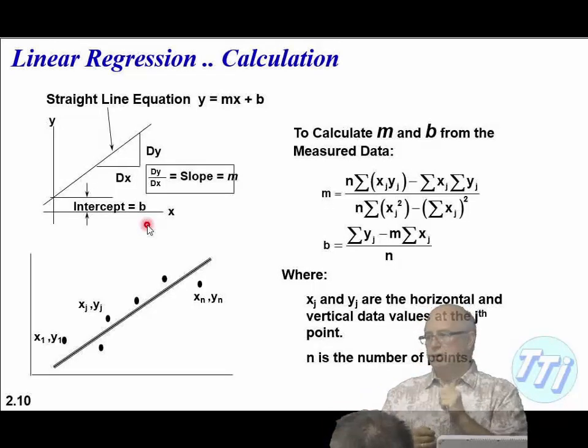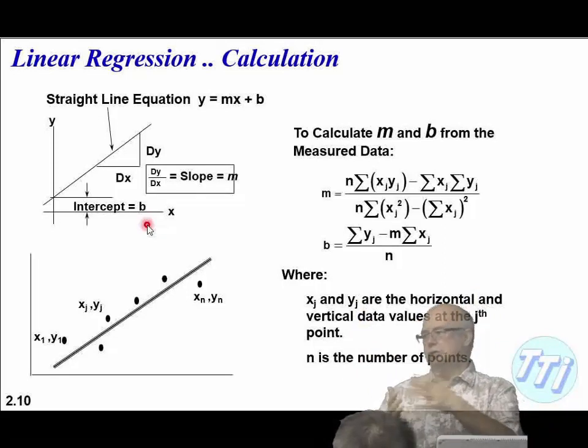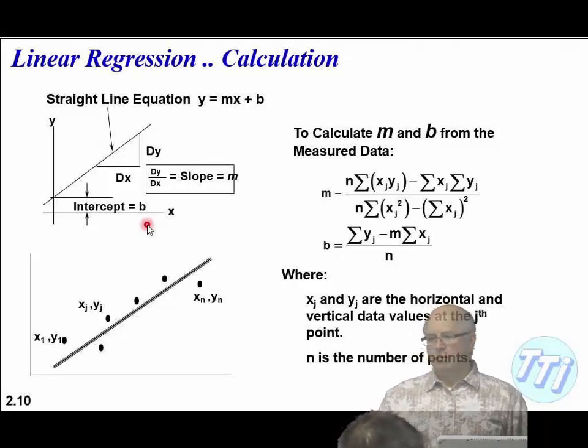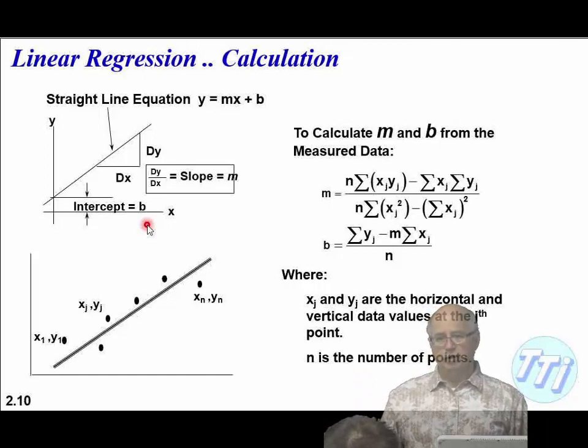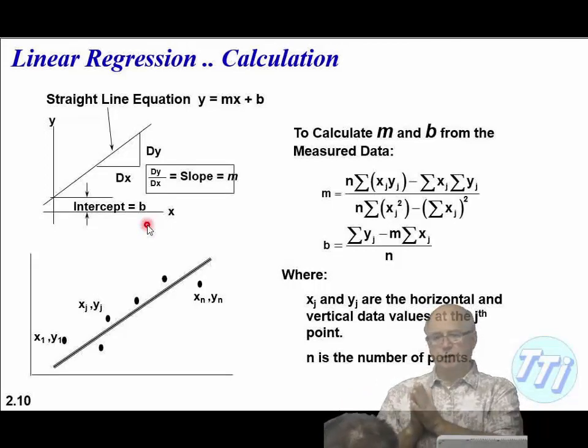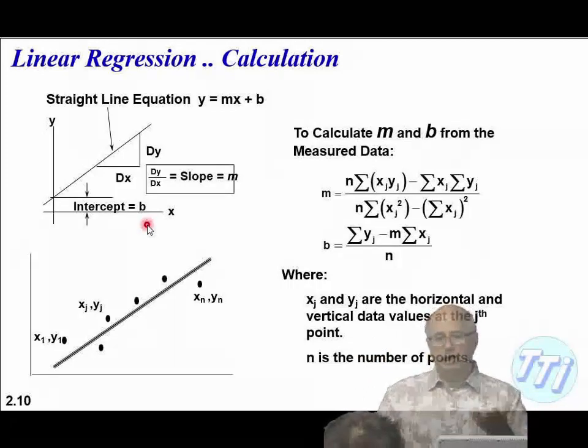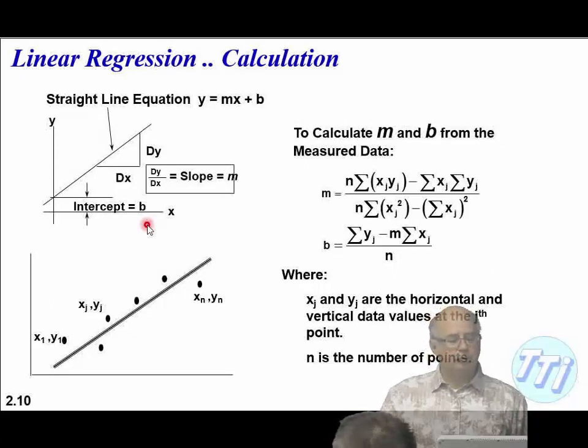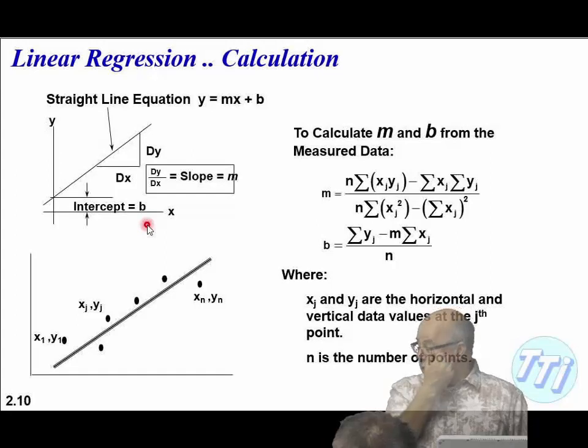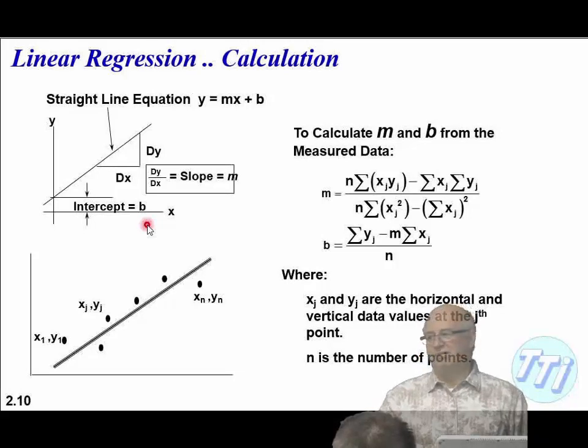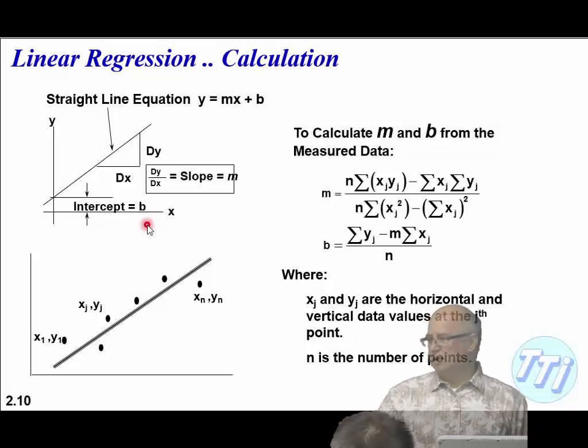One number by itself isn't really much use — you need a family of those over time. If the confidence intervals start to increase, something is going wrong with the calibration process or equipment. When I teach undergraduates linear regression in a measurements course, they all smile and say they've done it before. I say no, you haven't. They pull up Excel, put a regression line on, and I show them it doesn't work properly. Then we do all the error analysis.